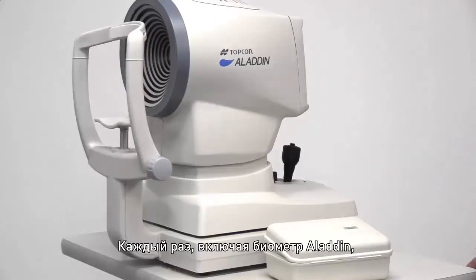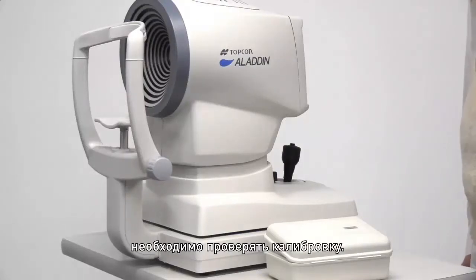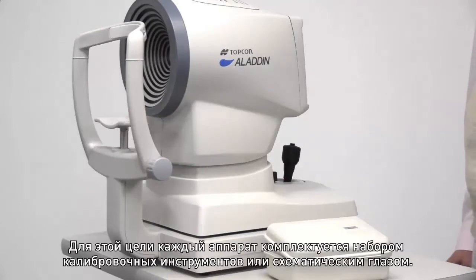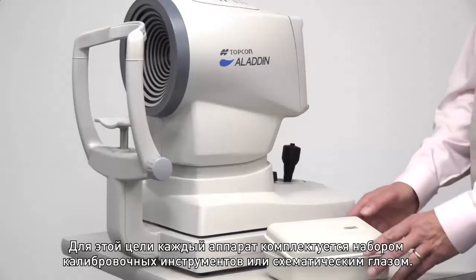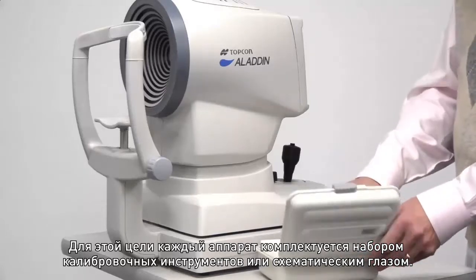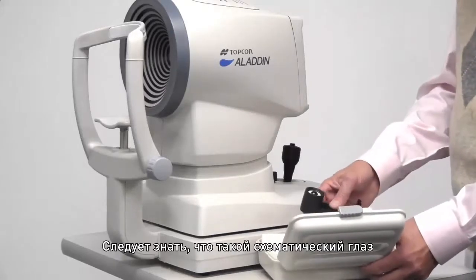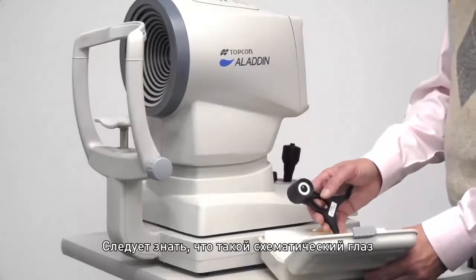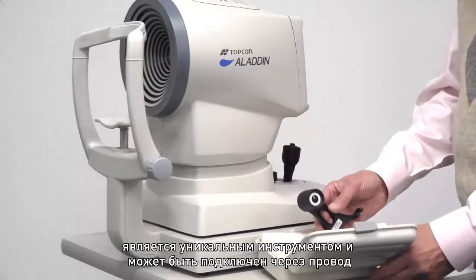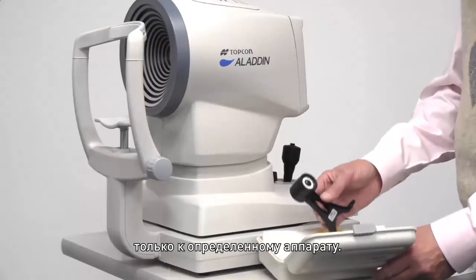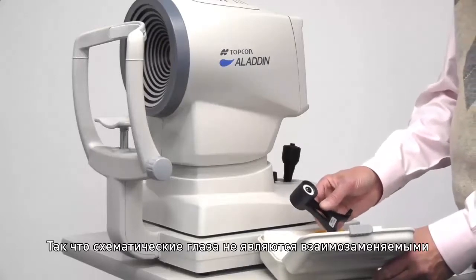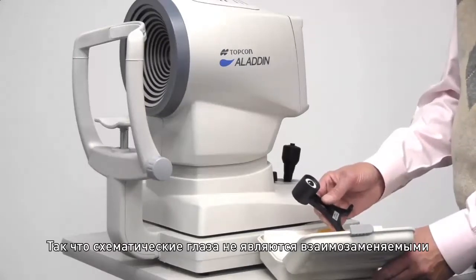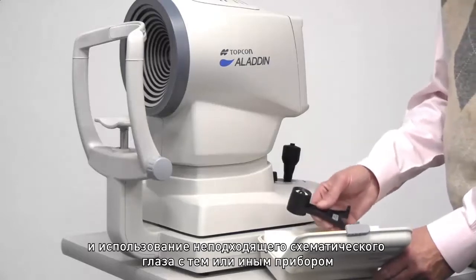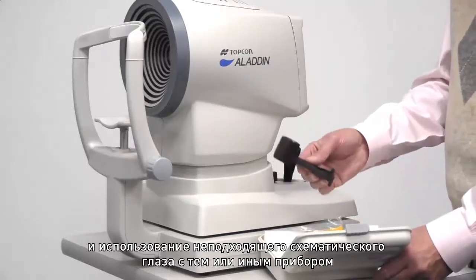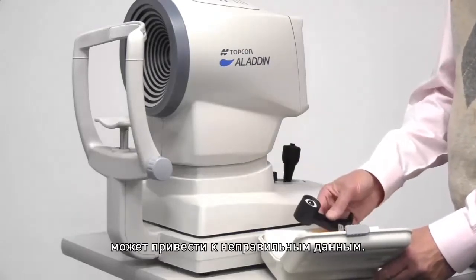Every time the Aladdin is turned on, it is important to check the calibration. For that purpose, each instrument comes with a calibration tool or schematic eye. It's important to notice the schematic eyes are unique to each instrument and they come coded with the serial number of the instrument, so the schematic eyes are not interchangeable, and using the wrong schematic eye in a different instrument could lead to mistaken readings.